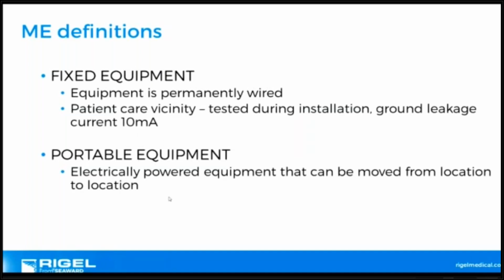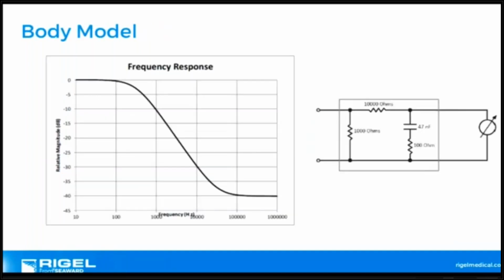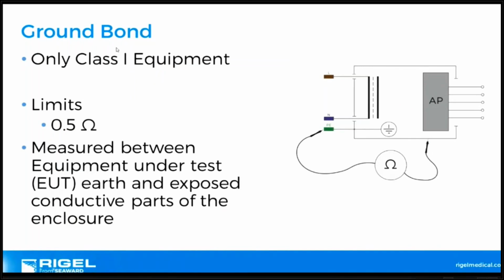Portable equipment is when by definition, you can move from location to location. So there's two different criteria of how you do your testing. Portable equipment is your typical 62353 or there and thereabouts. The body model is different. These characteristics here have a different frequency of response, but it's there and thereabouts, the same as 60601. We do ground bond or earth bond on class 1 equipment only. The limit is much higher. It's half an ohm, 500 milliohms, than 62353.